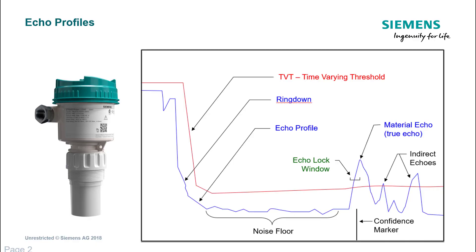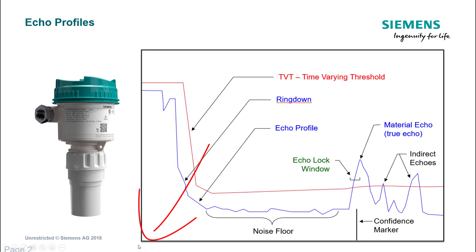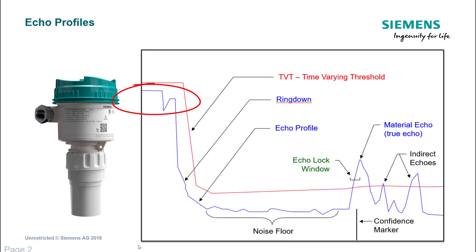The first thing we've got to understand is what we're actually looking at when we look at an echo profile. On PDM or the mobile IQ app, you'll have a trend that goes from left to right, where on the left hand side that's zero meters, and then on the right hand side it's your empty distance plus a little bit of far range extension. On the blue line we have a transmit signal and then we have something that we refer to on ultrasonics as ring down.